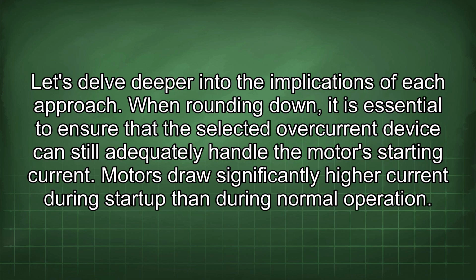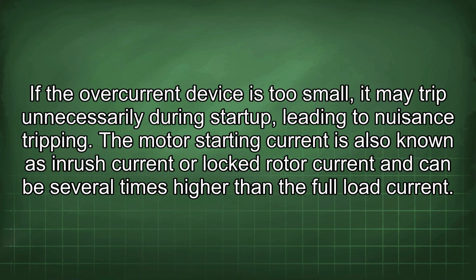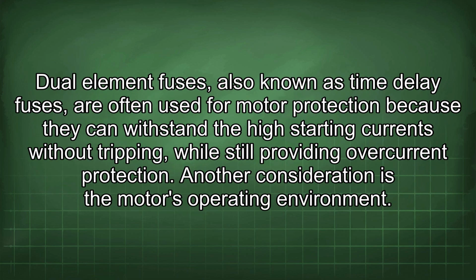When rounding down, it is essential to ensure that the selected overcurrent device can still adequately handle the motor's starting current. Motors draw significantly higher current during startup than during normal operation. If the overcurrent device is too small, it may trip unnecessarily during startup, leading to nuisance tripping. The motor starting current is also known as inrush current or locked rotor current and can be several times higher than the full load current. Dual element fuses, also known as time delay fuses, are often used for motor protection because they can withstand the high starting currents without tripping, while still providing overcurrent protection.